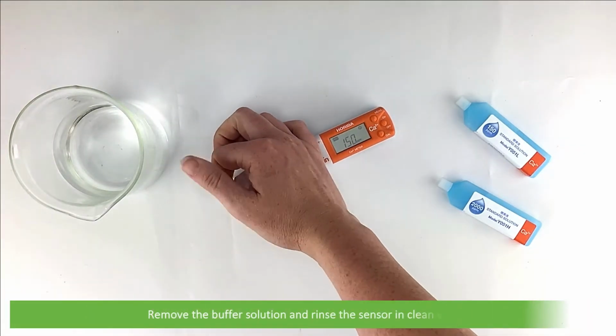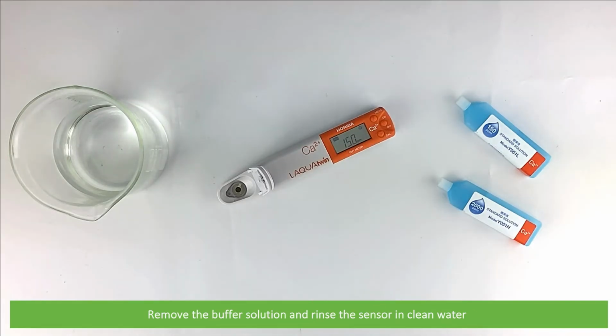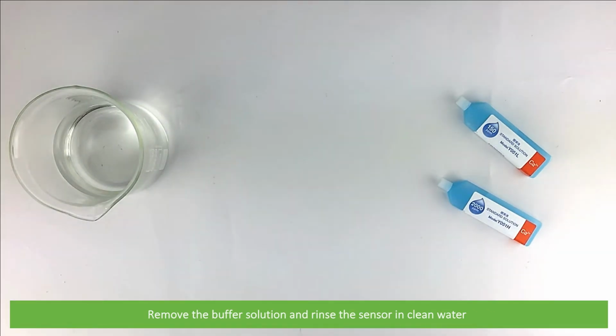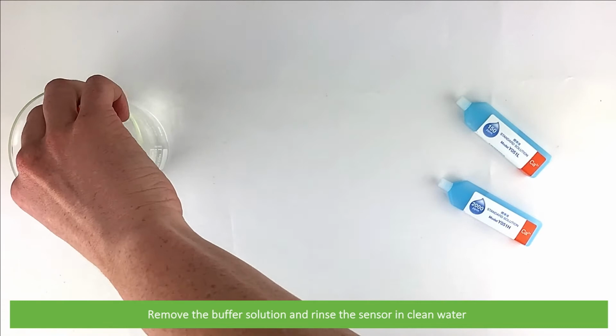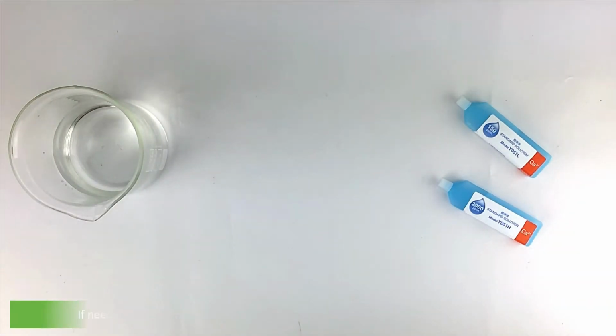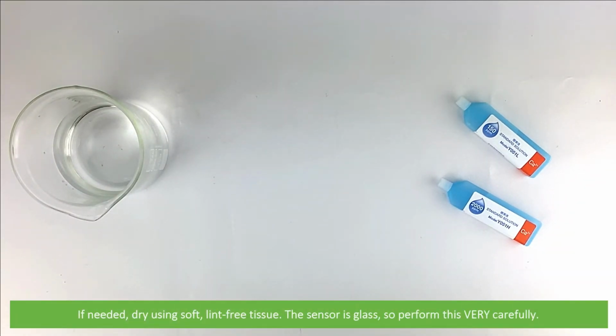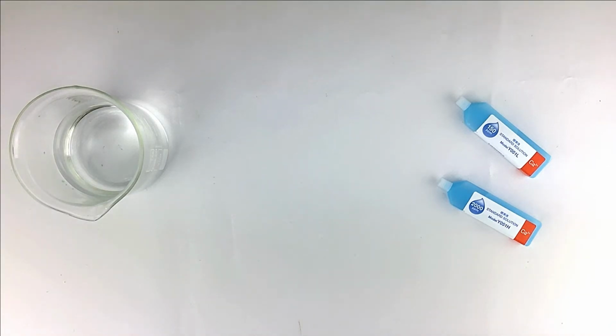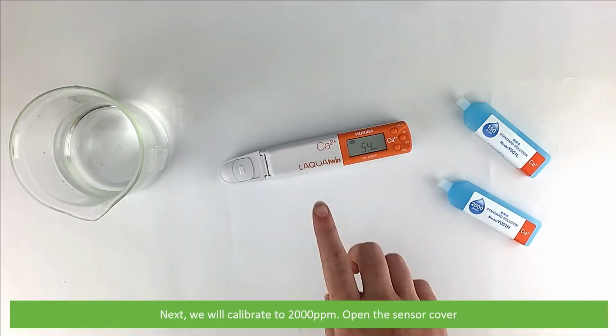Remove the buffer solution and rinse the sensor in clean water. If needed, dry using the soft, lint-free tissue, remembering that the sensor is glass, so perform this very carefully. Next, we will calibrate to 2000 parts per million.